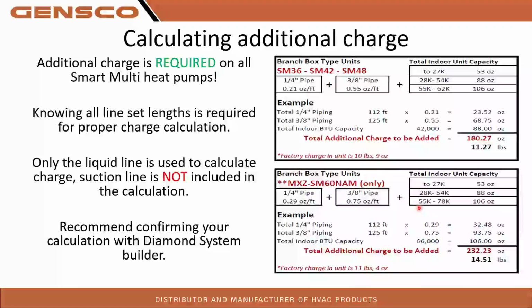After that, you're going to add up all of your indoor unit BTU capacity. So, your 9s, your 12s, your 15s, all those, add that together. And whatever your total is, you're going to use this little chart. And this is in all of your installation manuals, that book that comes with it, not an e-pad. What you do is add up all of your indoor equipment totals. Wherever you end up for a total capacity, you'll use this little chart.